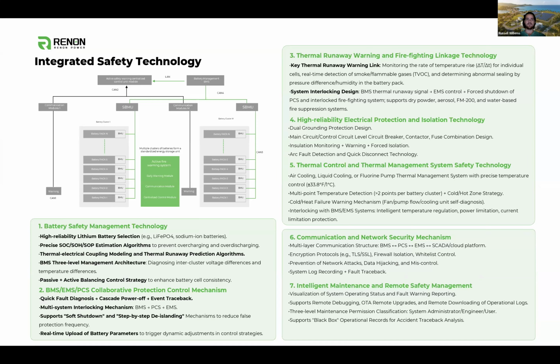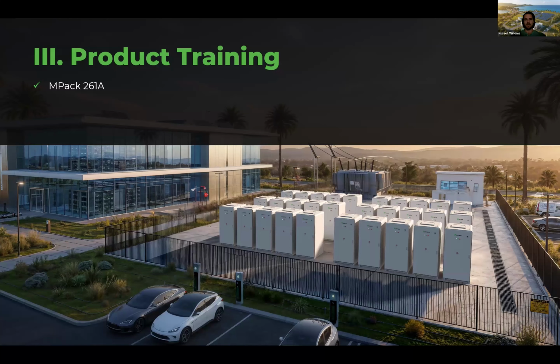The nice thing is that if you have a fault from, for example, a blip in energy production that might cause a cell to temporarily trip, the EMS is capable of self-monitoring. It'll continue to cycle and do a fault clear to validate there's nothing ongoing. So you don't have to do a truck roll every time a fault trips, it can self-clear and re-mitigate some of those issues on site.